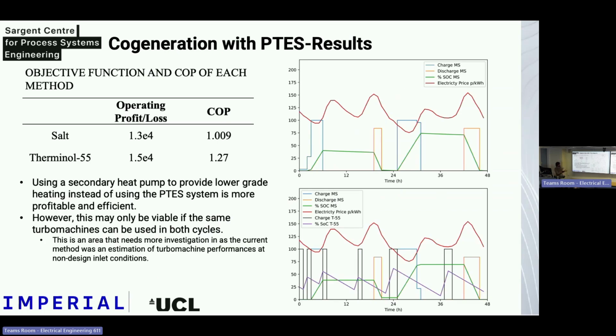We adjust this optimization problem slightly. If we supply the same constant heat supply over the duration, the operating profit is around 13,000, and the COP is around 1 using only the salt case. But with the heat pump with storage, in addition to the PTES system, the operating profit actually increases, and the COP increases as well.